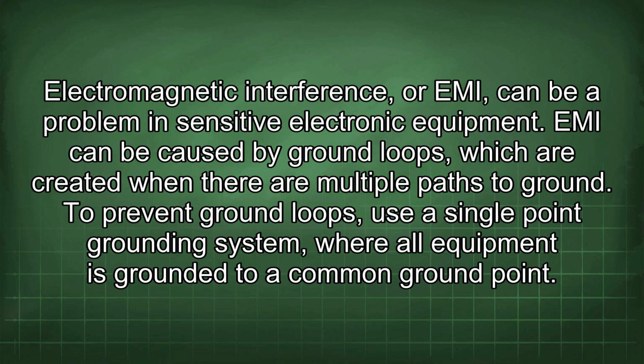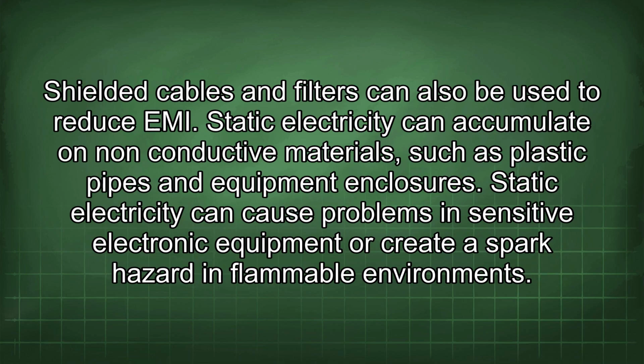Electromagnetic interference, or EMI, can be a problem in sensitive electronic equipment. EMI can be caused by ground loops, which are created when there are multiple paths to ground. To prevent ground loops, use a single-point grounding system where all equipment is grounded to a common ground point. Shielded cables and filters can also be used to reduce EMI.